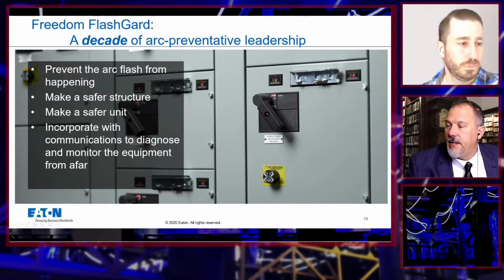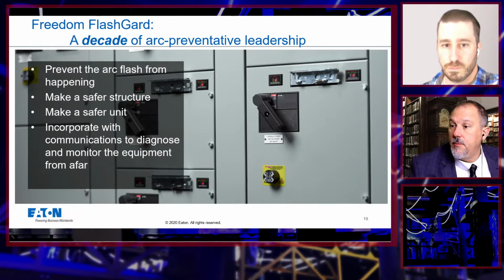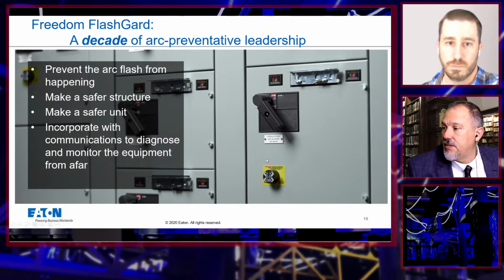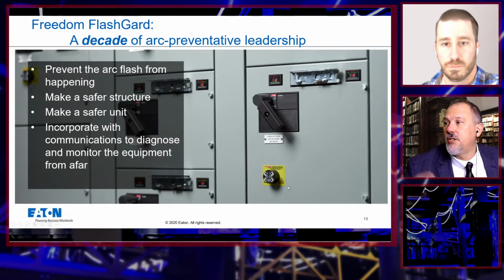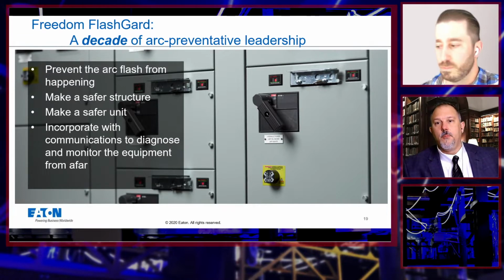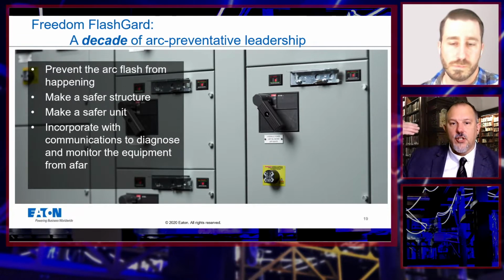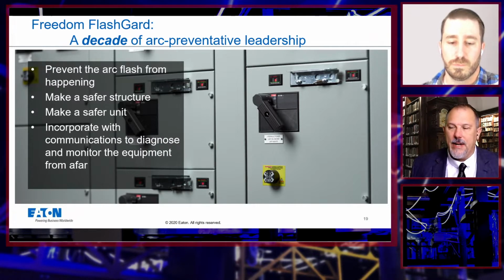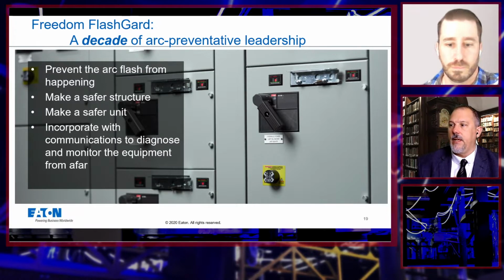So you want to prevent it from happening. You want to make a safer structure, safer unit, incorporate the communications, the diagnostics, and the presence of voltage. We're doing all these other things - we can get the electrical worker out of the arc flash boundaries, remotely operate things, remotely monitor the condition of things.